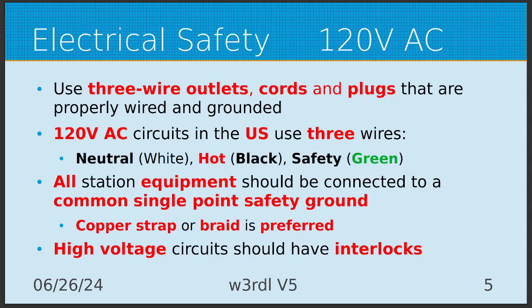If they're connected, they'll stay the same even if the ground is different and provides a slightly different route. Problems happen when your ground connection at the radio or antenna measures some ohms to ground, maybe only 2 or 3, while the utility ground is at 0 ohms. That difference will cause problems, so you want to keep them as close to the same as you can.